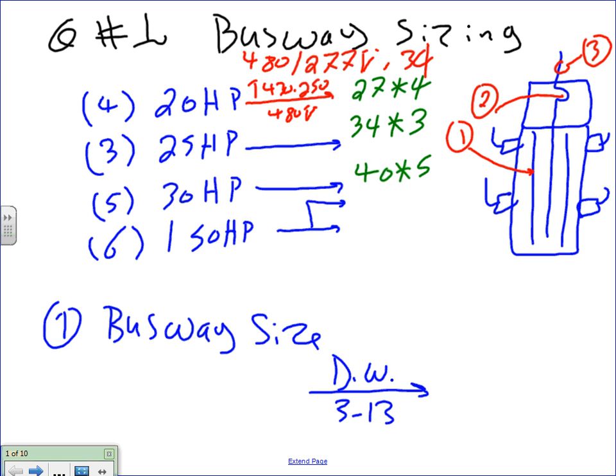So the first one is going to be 180. I'm going to multiply the 180 by, look what I did, 1.25. One, because there's 6 of them, I took 1, and the extra 25% on the largest motor. Right underneath it, also 180. Now, Nick, if I took 1 as the largest, the leftover from 6 is what? 5. So I multiplied it by 5. Any question what I did here to split? I took 1 out of the 6, 150, as the largest, fattest, fluffiest motor, and multiplied by 1.25 because it's the largest motor based on the code. And then the rest of them, it's 5. I multiply it by 5 because I took 1 for the largest. Any question about this little step? That's probably the confusing one, if there's anything to be confused with.